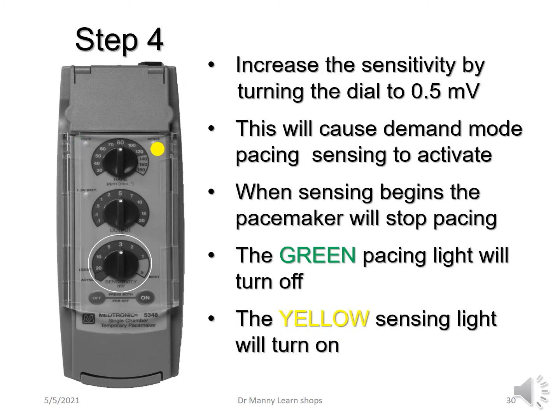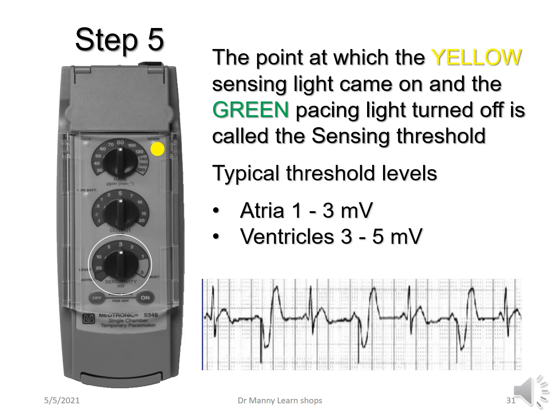Then you increase the sensitivity by turning the sensitivity dial to 0.5 millivolts. This causes demand mode pacing to occur and sensing to be activated. When sensing begins, the pacemaker will stop pacing — the green light turns off — and as soon as sensing commences, the yellow light comes on. Step five: this is the point at which the yellow sensing light came on and the green pacing light turned off — this is the sensing threshold. Typical sensing thresholds are one to three millivolts in the atria and three to five millivolts in the ventricles.